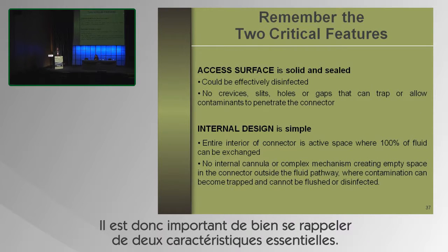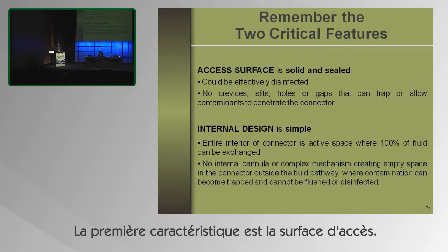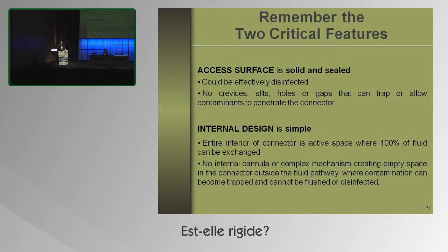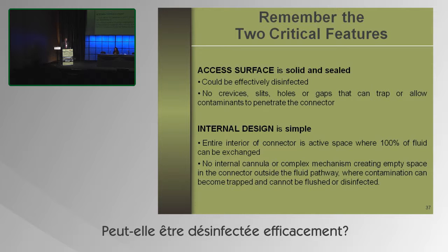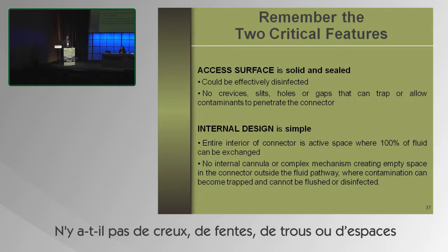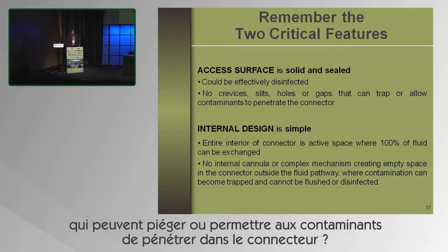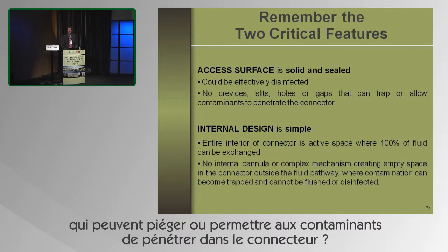So it's important to remember these two critical features. First is the access surface. Is it solid and is it sealed? Can it be effectively disinfected? There are no crevices, slits, holes, or gaps that can trap or allow contaminants to penetrate that connector.